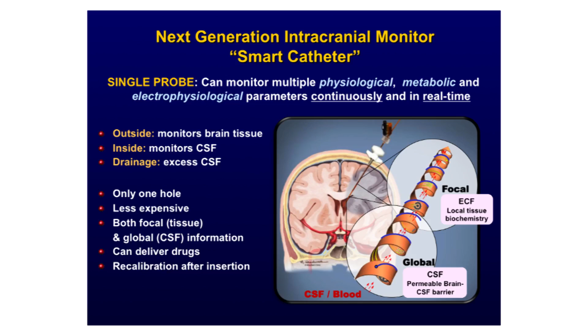And if we were to accomplish this, it would be with one hole, perhaps less expensive. We can monitor both the focal tissue parameters and the CSF. We can also deliver drugs through this if a drug became available that one might want to inject directly into the brain. And one other major problem with the monitors has been that if you put in a monitor which has no fluid coupling, once you put that thing in, it's a leap of faith. You do not really know whether it is accurate or whether there's been a drift. Whereas with this technology, we should be able to recalibrate it any number of times so that we can be sure that when you're reading a pressure of 20, which is considered the upper limit of normal inside the head, 20 millimeters of mercury, we are in fact at 20 and it's not actually 40 and you're getting a false sense of security.